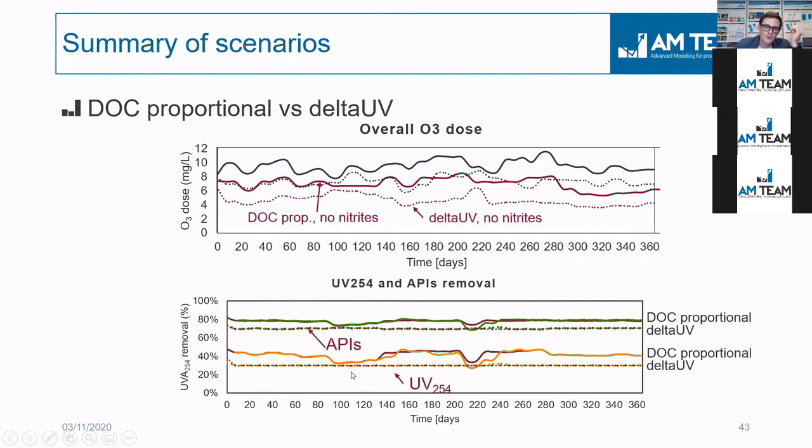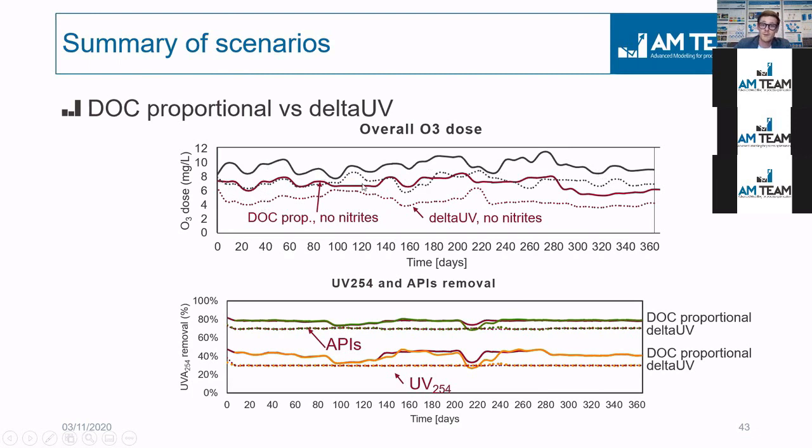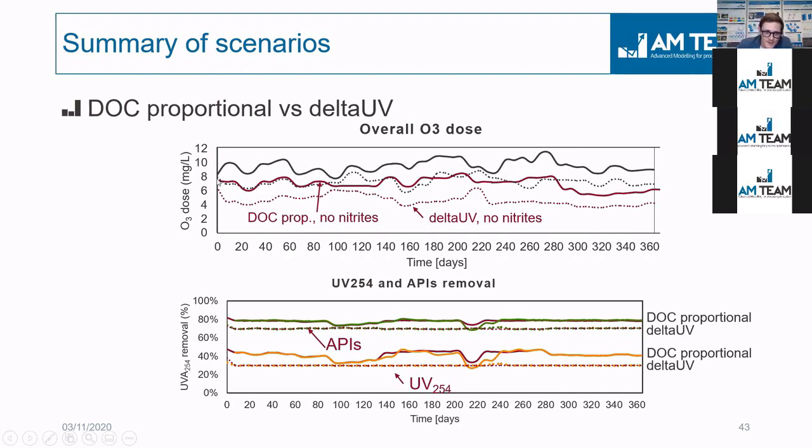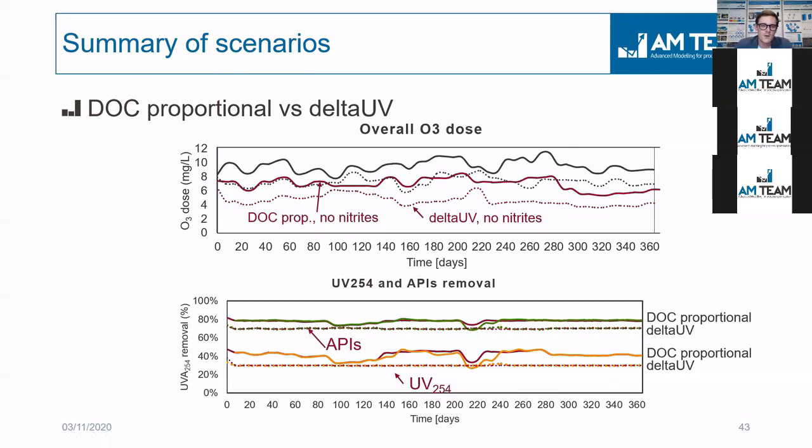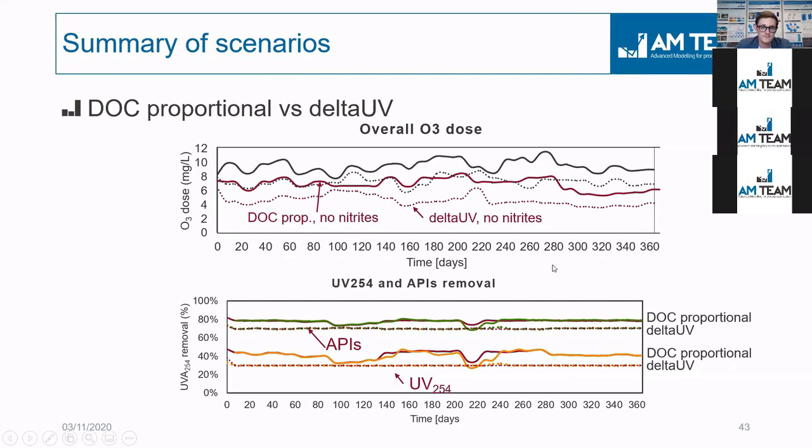And just hypothetically, what would happen in this plant if there were no nitrites? Well, you can see the same curves, these brown ones, dropping quite significantly. And these are, let's say, the Bordeaux curves here, which are of significant lower ozone dose. So with a very low ozone dose, actually, you get the same API or pharmaceutical removal. In this specific plant, nitrites had quite an impact, because the levels were quite significant. So this is really, really important, and if you look at effluent treatments.